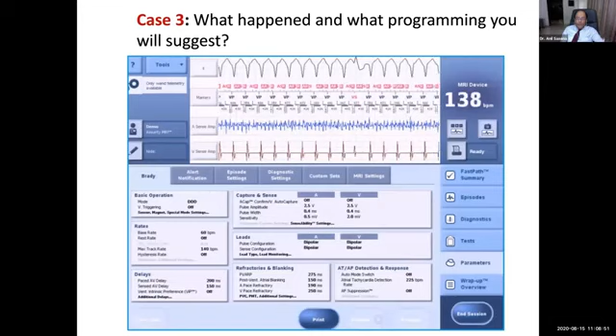So what is automatic mode switching? It is basically the ability of the pacemaker to automatically switch from one mode to another in response to a sensed atrial tachyarrhythmia. When we want to program this, we have to program two things. One, an AT detection rate, that is, at what rate the pacemaker will implement the mode switch. And second, we have to decide what non-tracking mode we want. Usually in a dual chamber, it's a DDIR mode, where the pacemaker will not track, but will maintain an adequate heart rate during activity.